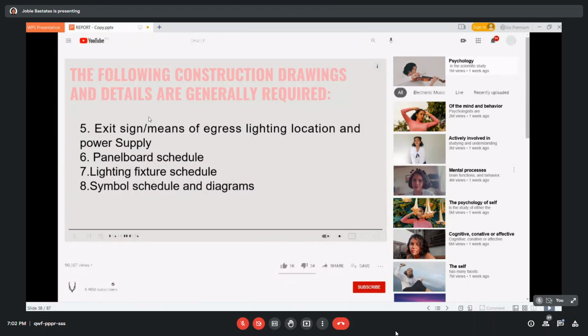Seven, lighting fixture schedule. A light fixture schedule can be displayed on the drawing. The schedule lists all the light fixtures used in the project. Eight, symbol schedule and diagrams. The advantage of having this is that it will only display the symbols that are actually in use. Using an interactive schedule makes a more compact, relevant, and readable table.